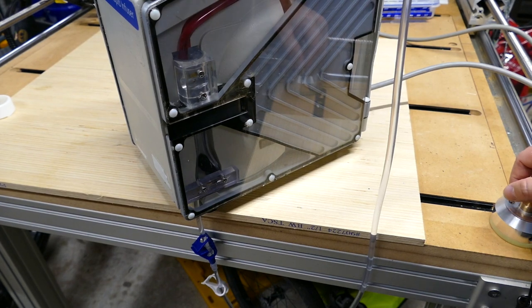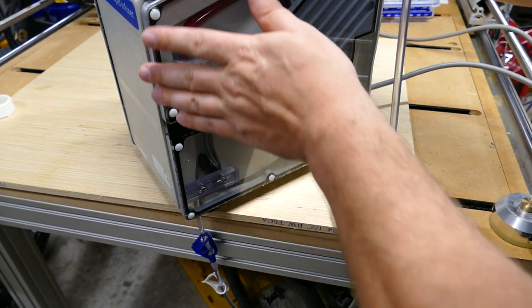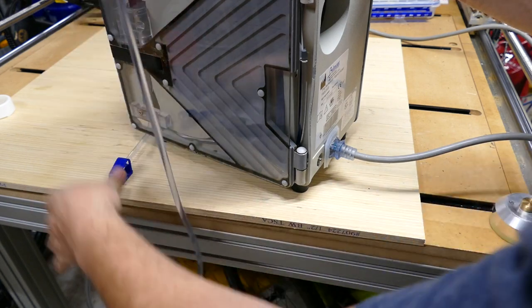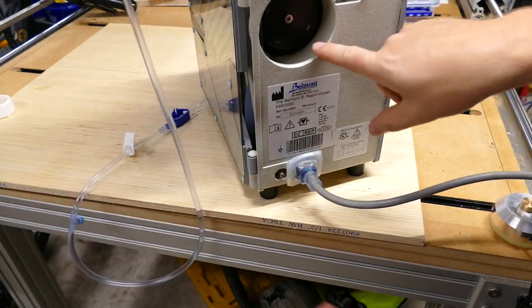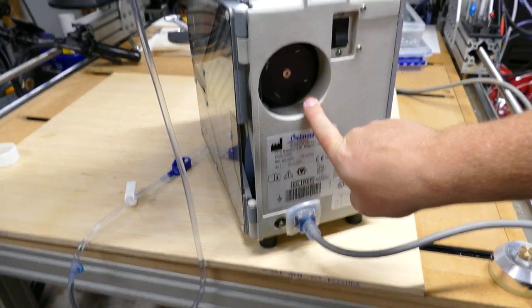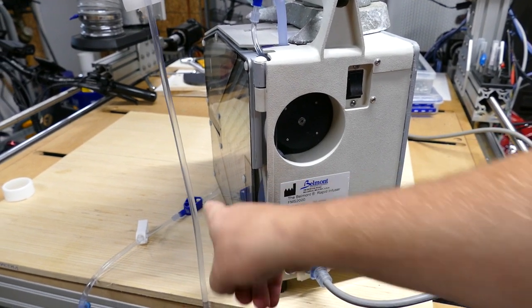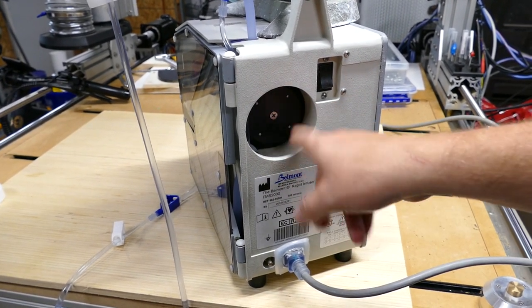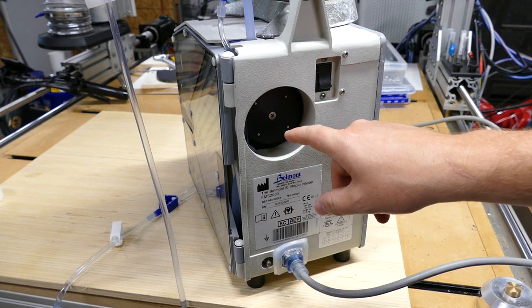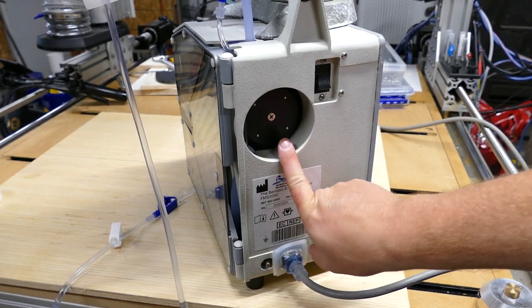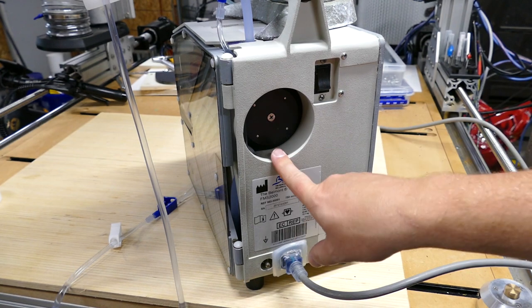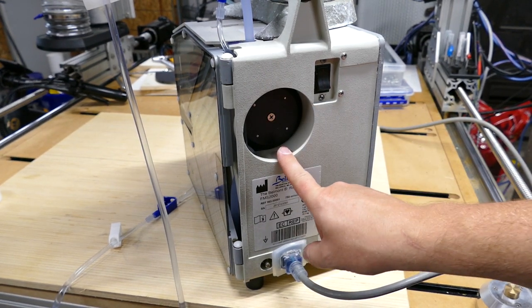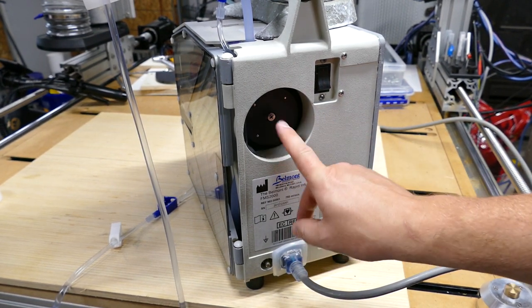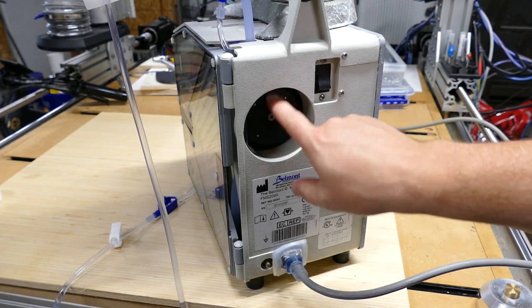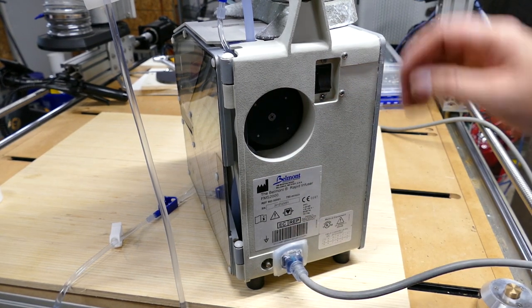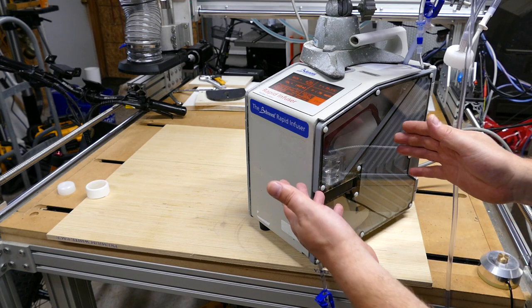Now, one of the features I want to point out to you guys about this system is that the peristaltic pump is exposed on the back. It's going to throw an error code because I pinched the line down there. But the peristaltic pump is exposed on the back. And one of the ways that we can calibrate this unit is by using RPM to determine flow. So you do not need a flow meter to calibrate this unit. We can actually do it with a photo tachometer and that exposed pump head. So that's the function of the unit.